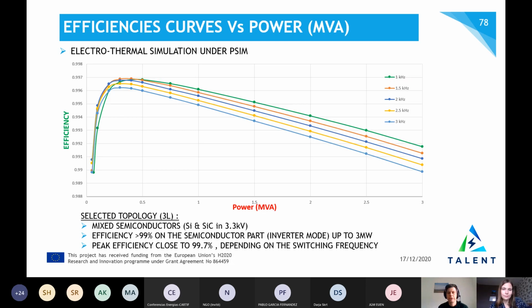This is the efficiency curve we simulated by electrothermal simulation at several switching frequencies on the SiC MOSFETs, from 1 kilohertz to 3 kilohertz, and you can see that very high efficiency on the semiconductor side can be reached, superior to 99% for power from a few hundred kilowatts up to 3 megawatts. So we can expect good performance with this topology.